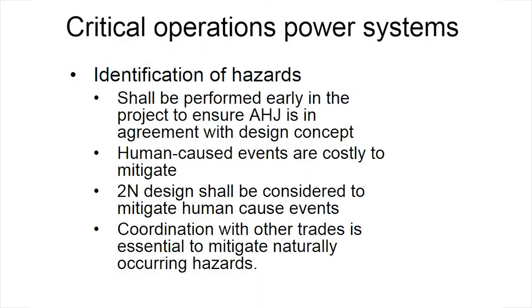It's also important to coordinate with other trades regarding your risk analysis. We have learned many things: what kind of protection you're going to have on your building, how you are going to protect your generator, whether it should go inside the building, and what about your cooling. Should it be cooling towers, or do you want to use air-cooled chillers so they go inside the building and are protected against natural disasters, especially if your facility has to do with natural disasters. You have to figure out what kind of facility you're doing, and when the facility is going to be used the most, and then make sure your design correlates with that need. It is really important, and you've got to do it early in the process.